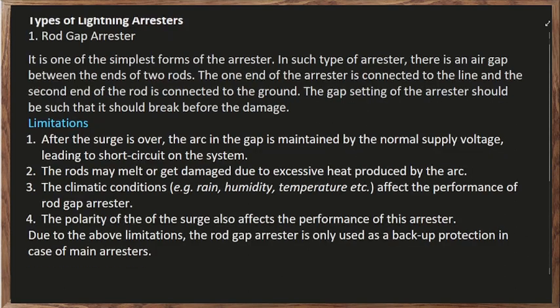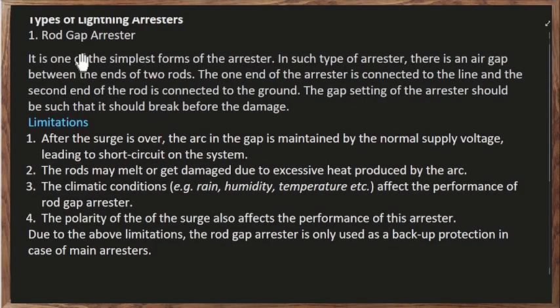Okay, so we have types of lightning arrestor. We have the rod gap, which is the simplest form of arrestor. The limitation is, after a switching surge is over, the air gap is maintained by normal supply voltage, leading to short circuit in the system. Now, the rods could also melt or get damaged due to excessive heat produced by the arc. Then it could also be affected by the climatic conditions. Then the polarity of the surge also affects the performance of the arrestor.